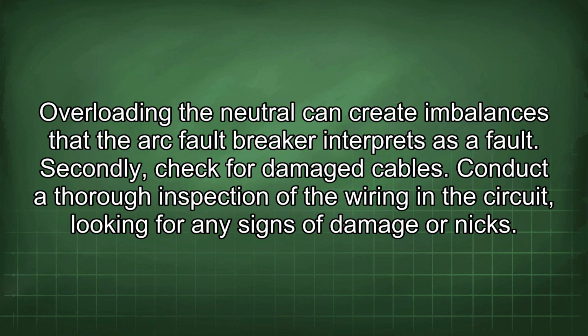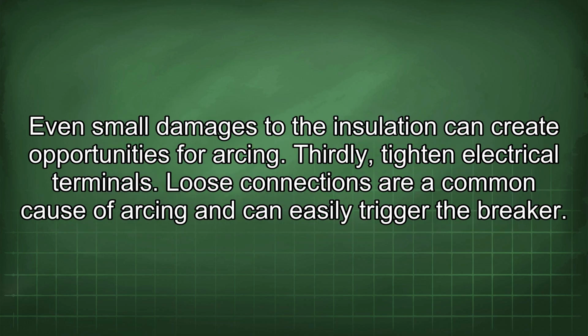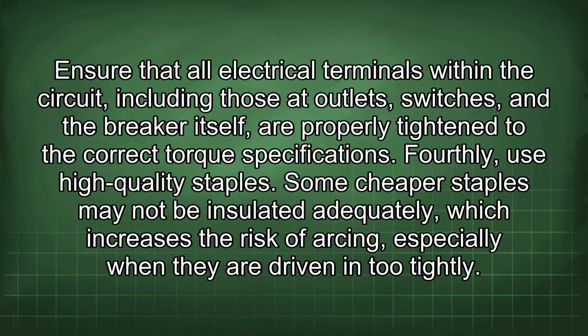Secondly, check for damaged cables. Conduct a thorough inspection of the wiring in the circuit, looking for any signs of damage or nicks. Even small damages to the insulation can create opportunities for arcing. Thirdly, tighten electrical terminals. Loose connections are a common cause of arcing and can easily trigger the breaker. Ensure that all electrical terminals within the circuit, including those at outlets, switches, and the breaker itself, are properly tightened to the correct torque specifications.